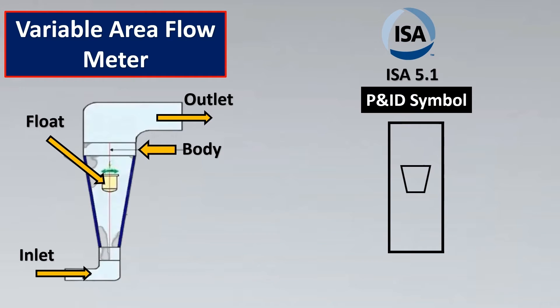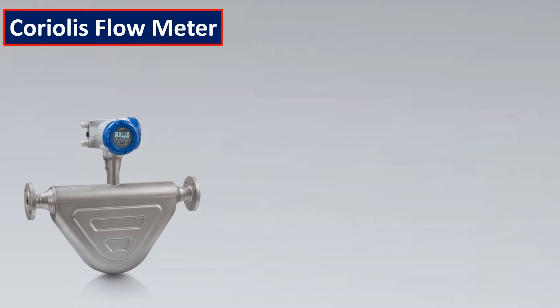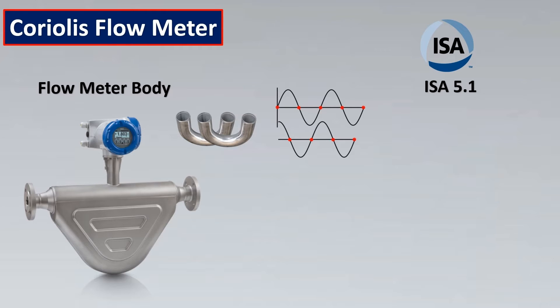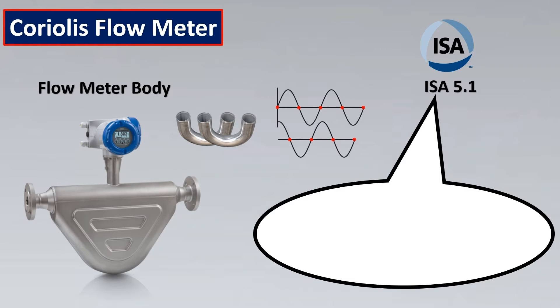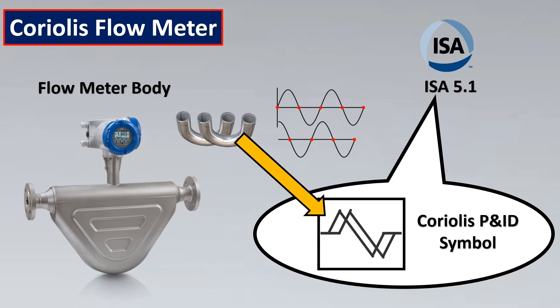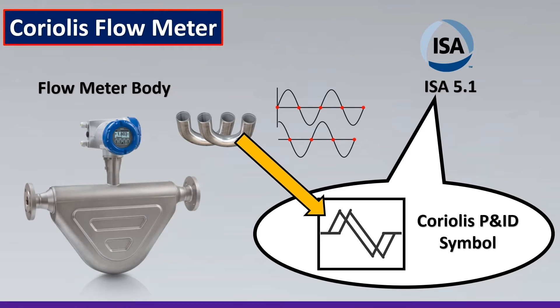The next symbol is for the Coriolis flow meter. Inside the meter body are tubes that vibrate and oscillate — the more they are out of phase, the higher the flow. ISA 5.1 has done something amazing: they mimicked this working concept in the symbol, where the tubes are represented with an oscillating shape and the body is shown around them. This is your Coriolis P&ID symbol.